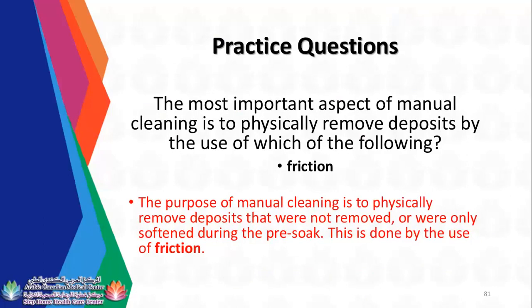So either you are doing the pre-soak, or at the point of use they are putting some foam or enzymatic foam just to keep it moist. Okay, it doesn't mean that the soil has already been dissolved by the pre-soaking or the spray. You will not skip the manual brushing. So you will do the manual brushing, and one of the main purposes of that is to provide friction within the instruments with the brush, so that any loosened debris can be removed. Any fine debris that cannot be removed in your manual brushing can be removed in your ultrasonic cleaning.